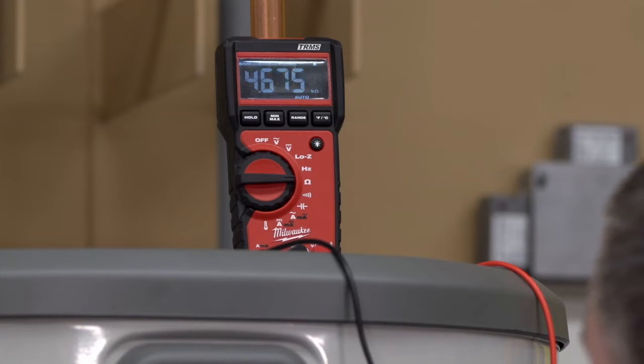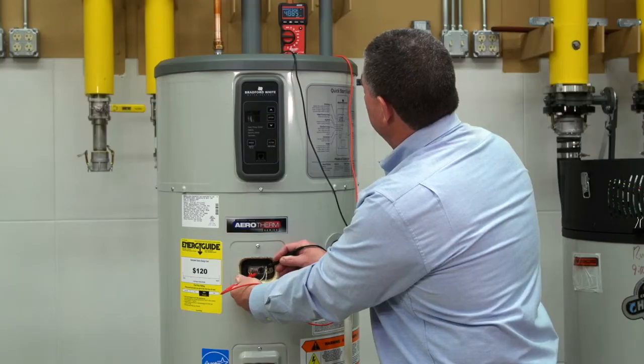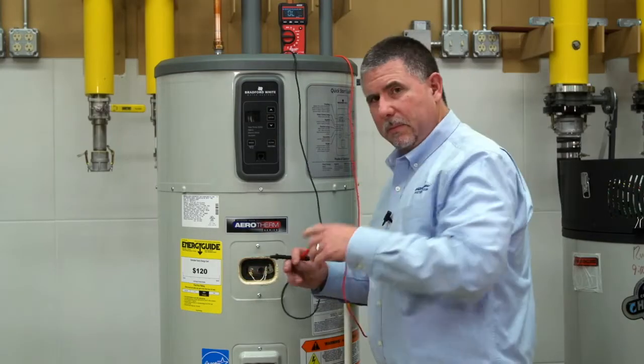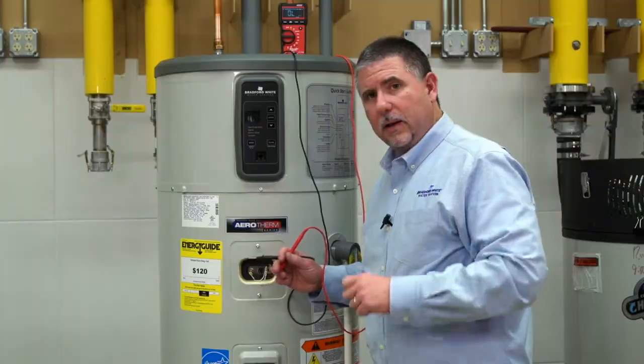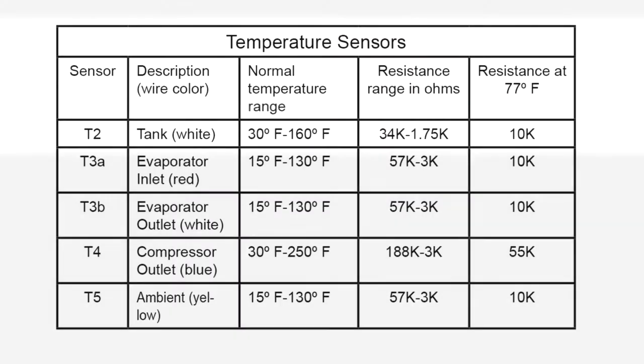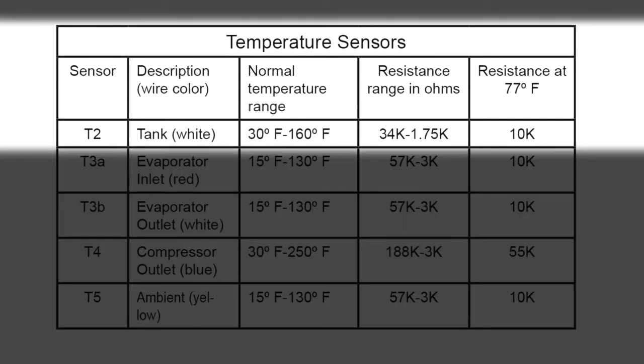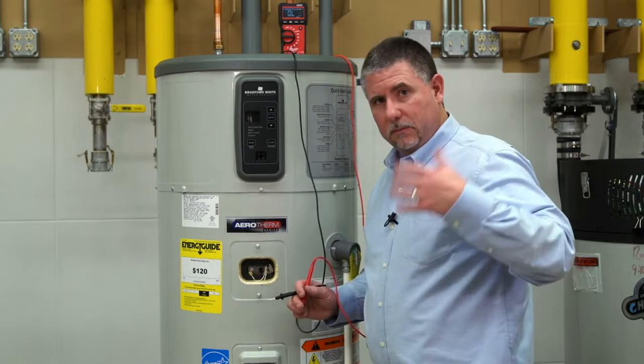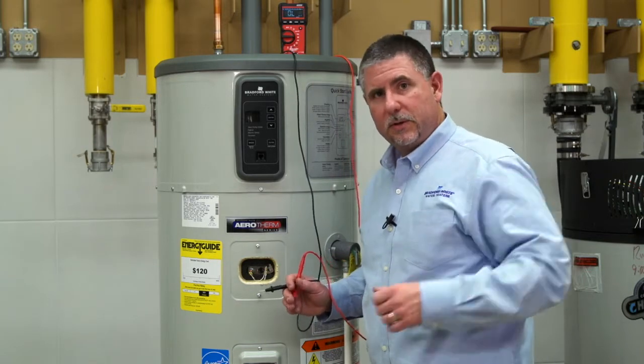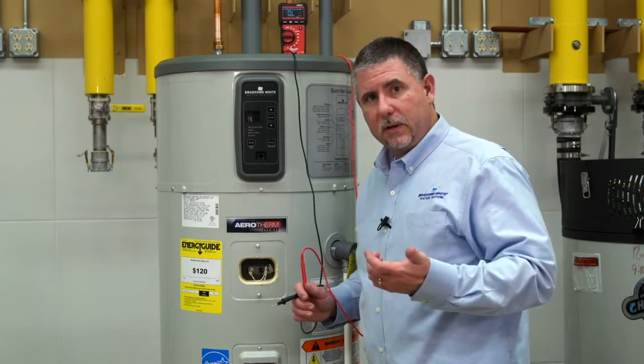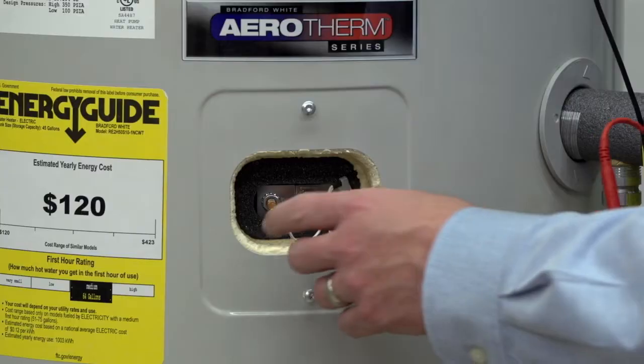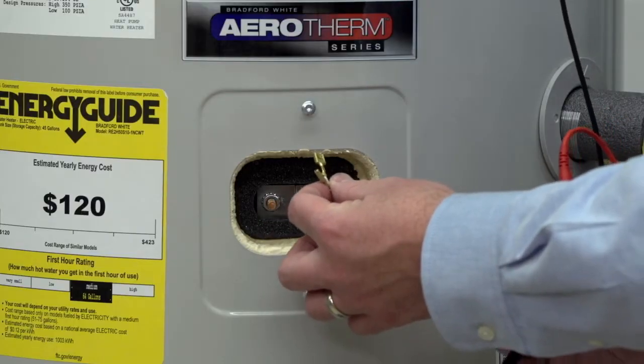Okay. Here I've got somewhere, it looks like it's climbing a little bit, right? So I'm going to be right around 5K, right? That 5K resistance, or 5,000 ohms, will correlate to a temperature. That's what the board is doing, is it's calculating a temperature. So the sensor says we're 5K. We go to our temperature chart and verify that. If that's a realistic and believable number, we need to measure continuity of our white wires.